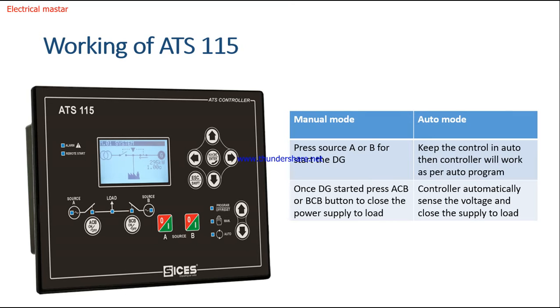Now let's see how the ATS 115 works. The ATS 115 working is very simple. It has two modes: one is the manual mode, another is the auto mode. If you look at the picture, there are two arrows, up and down arrow. You can see this LED. When the LED is on the first one, that is the off mode. You just press the down key to bring it to the manual mode.